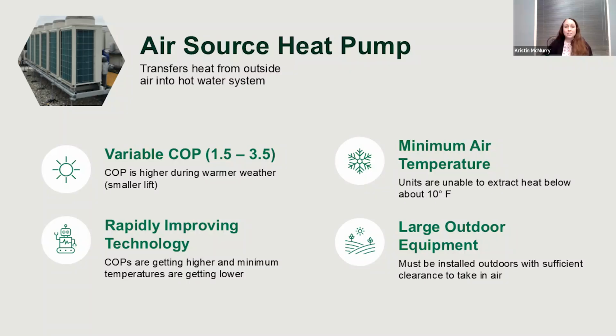What it does is extract heat from the outside air and put it into the hot water system. You can use it for cooling, but the COP is lower than you get even for an air-cooled chiller, so you just wouldn't use it for that, though you could. The COP for heating is going to be better when there's more heat in the air, which makes sense—the warmer it is outside, the better the COP.